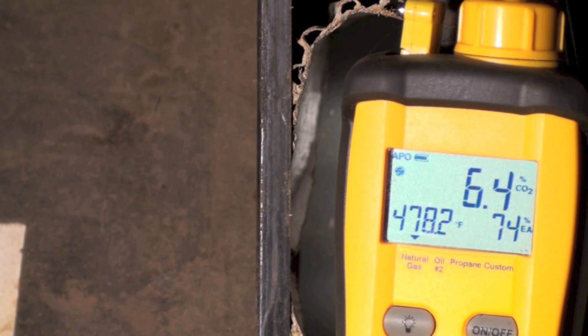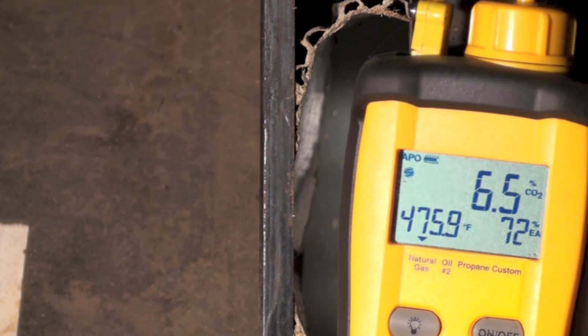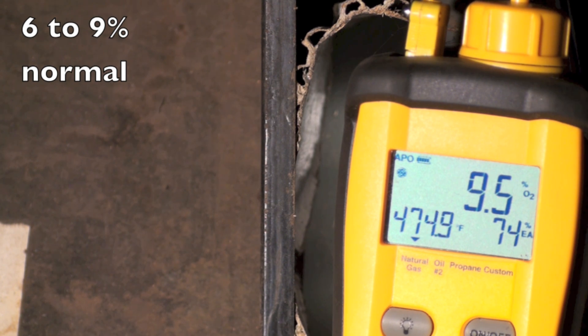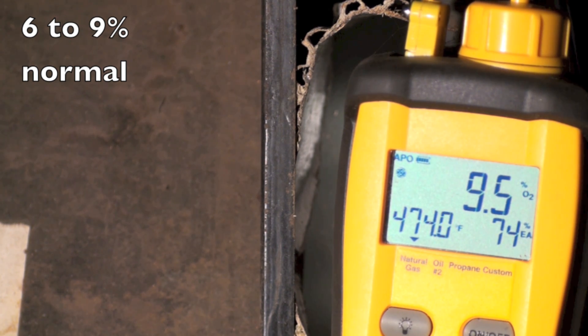Okay, again we're checking the burner that has the wide open primary air. Okay, CO2 - 6.5, O2 - 9.4 or 9.5. Okay, the stack temperature - wow, stack temperature is way down, isn't it? 474.